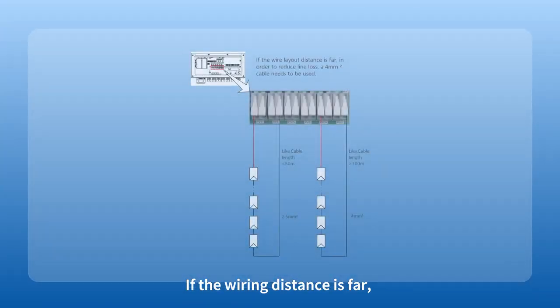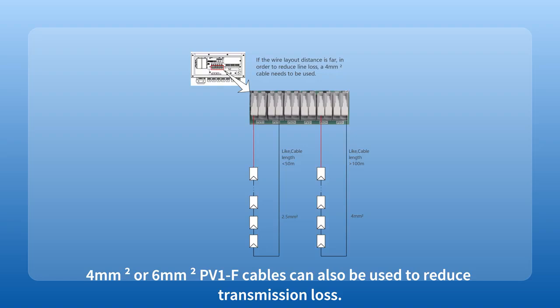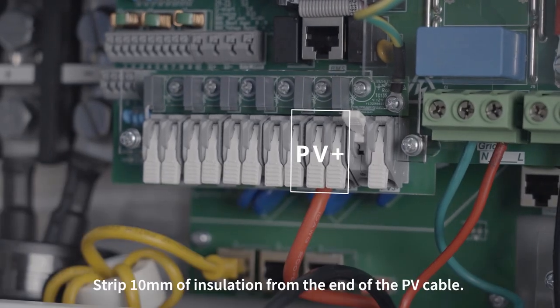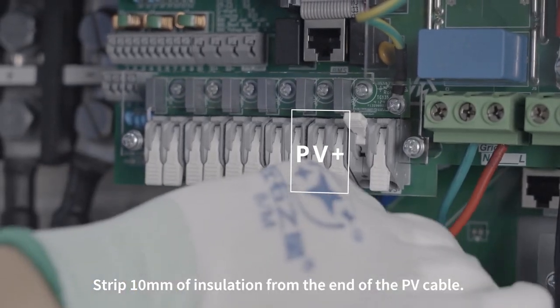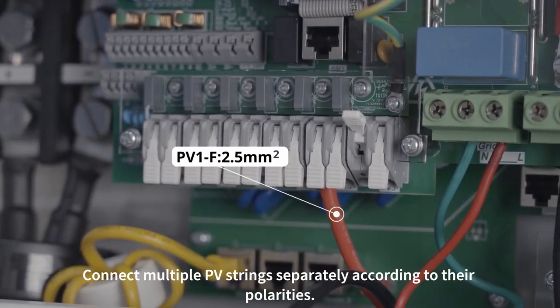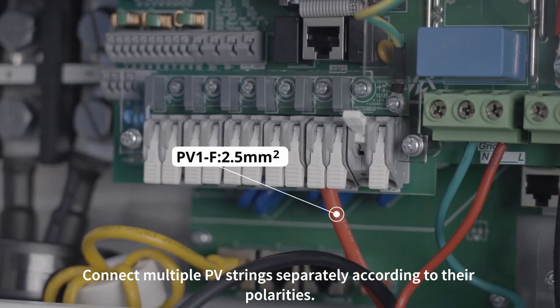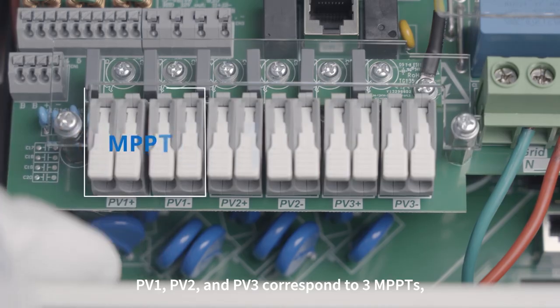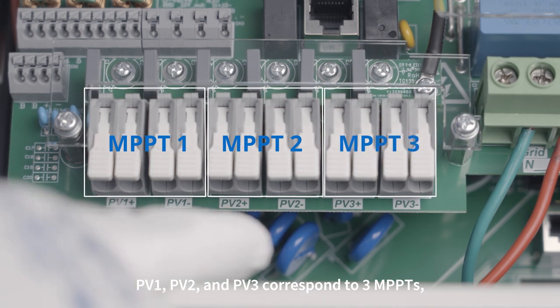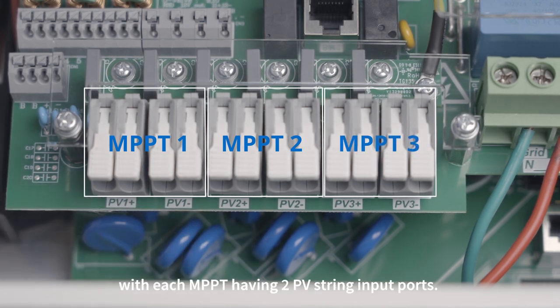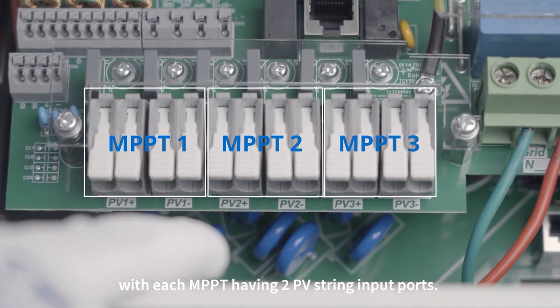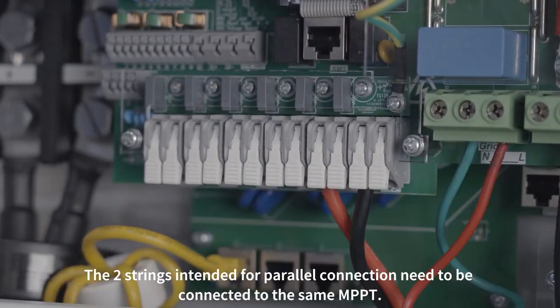If the wiring distance is far, 4 mm squared or 6 mm squared PV1F cables can also be used to reduce transmission loss. Strip 10 mm of insulation from the end of the PV cable. Connect multiple PV strings separately according to their polarities. PV1, PV2, and PV3 correspond to 3 MPPTs, with each MPPT having 2 PV string input ports. The 2 strings intended for parallel connection need to be connected to the same MPPT.